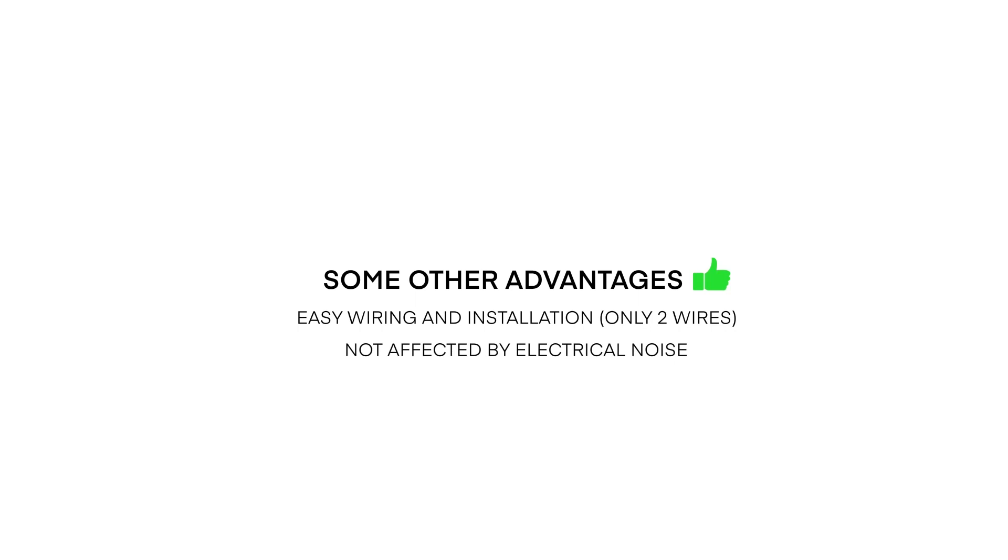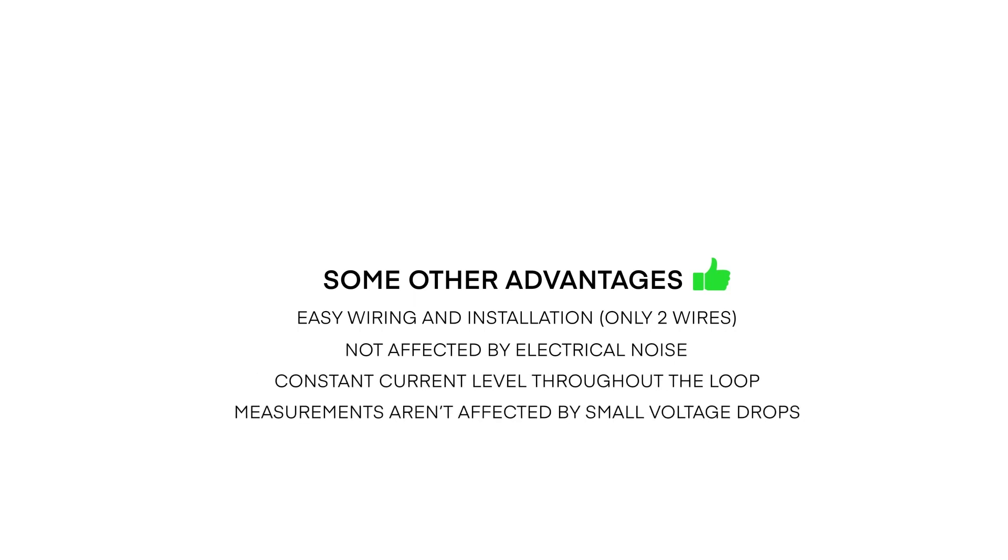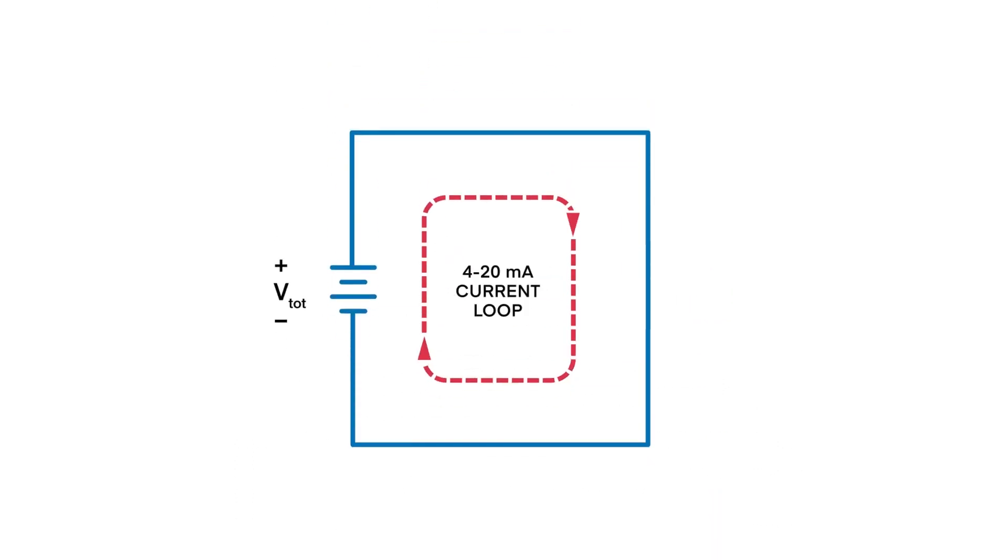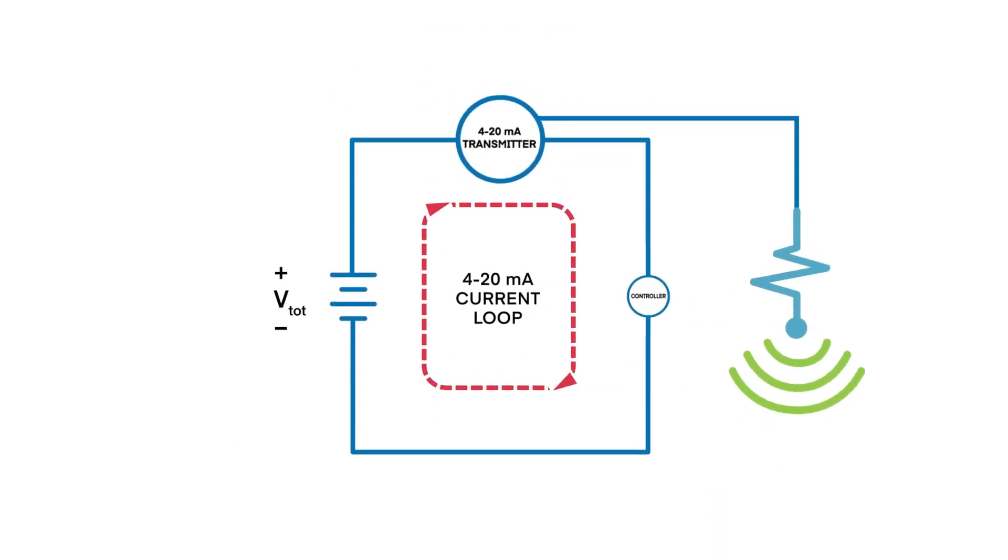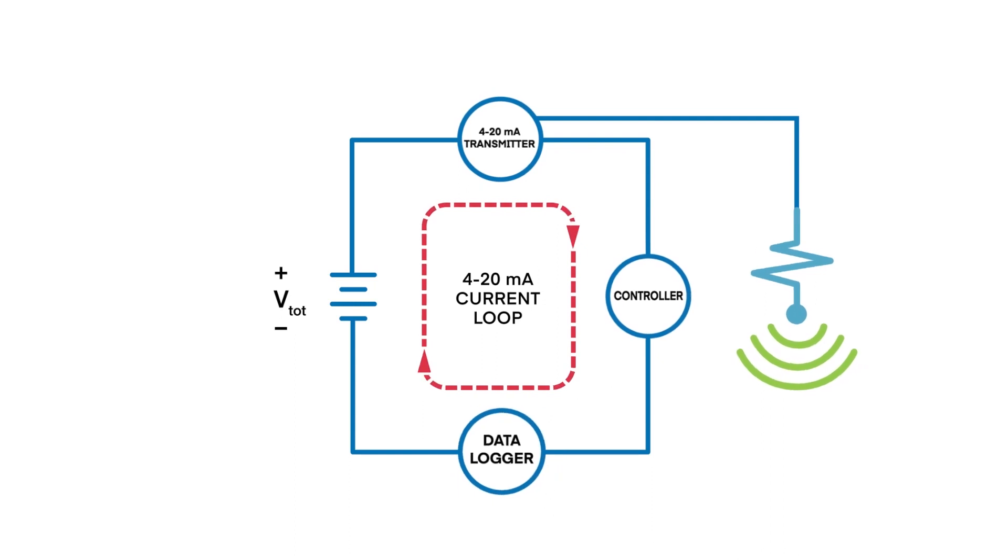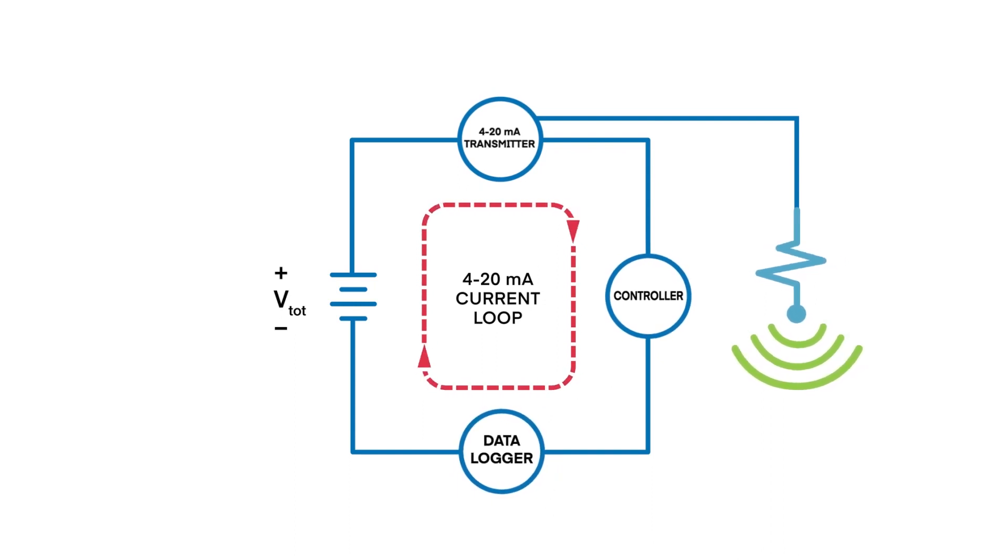They're not affected by electrical noise, and since the current level remains the same throughout the loop, measurements aren't affected by small voltage drops across other devices on the loop. And the only limitation to the number of devices is the amount of voltage from the power supply driving the current loop.